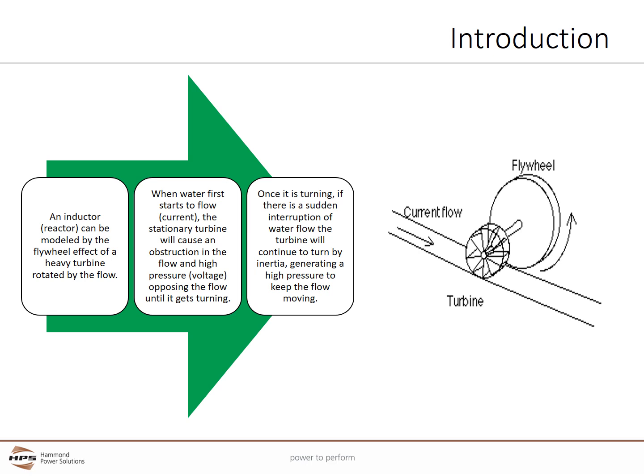While this appears to be a complicated picture, a reactor basically slows changes in currents. By smoothing out current flow, a reactor can help mitigate current harmonics and improve power quality on the line side of a VFD and can protect the VFD from voltage spikes. A load reactor between the VFD and the motor helps protect the motor from several issues, including the reflective wave phenomenon.